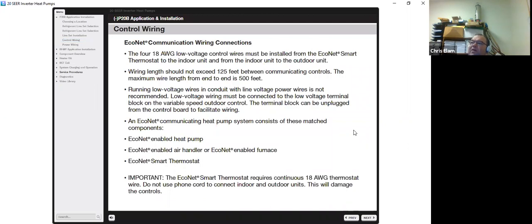For the EcoNet communication wiring, all that is required is 4 18-gauge low voltage control wires from the EcoNet thermostat to the indoor unit and then also to the outdoor unit. The wiring length should not exceed 125 feet between communicating controls. The maximum wire length is 500 feet. Running low voltage in conduit with line voltage power is not recommended. You can and probably will have some communication issues.